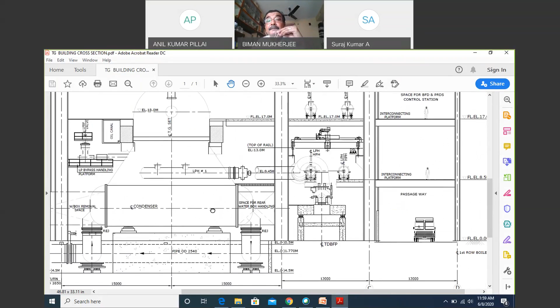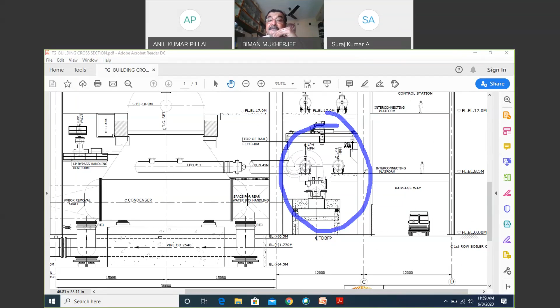This is the boiler feed pump, which is basically turbine driven, so it doesn't consume a lot of power. For a 1,000 megawatt unit, you have about 80 megawatts of internal consumption. Whatever you can utilize through steam tapping from different places makes the efficiency better.